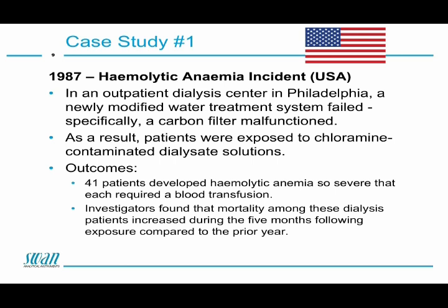But this case study occurred in America in 1987, and so in an outpatient dialysis center in Philadelphia, a newly modified water treatment system failed. Specifically, a carbon filter malfunctioned. Now, we don't know if they had an RO process happening at the same time. Possibly not in 1987, but as I said, the carbon filters are normally the primary barrier.